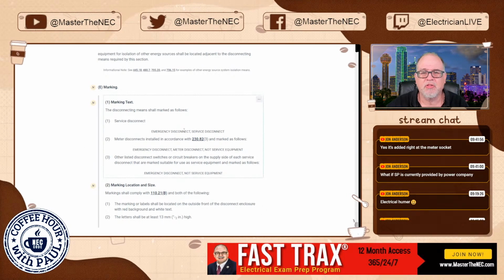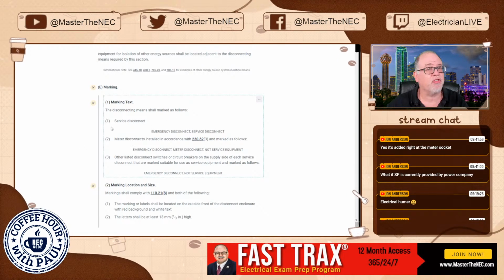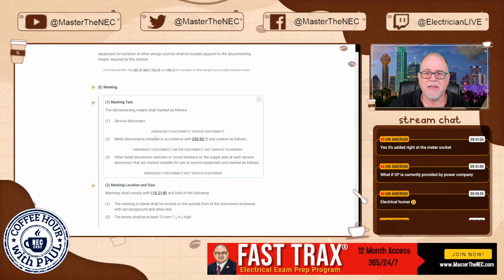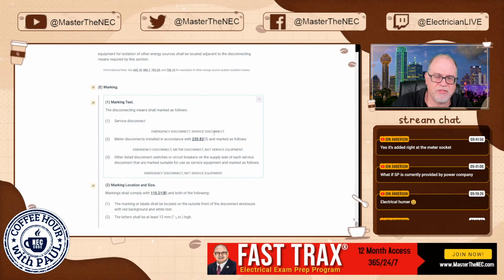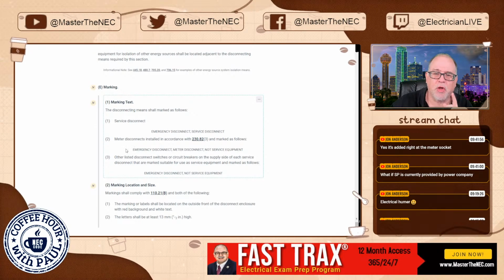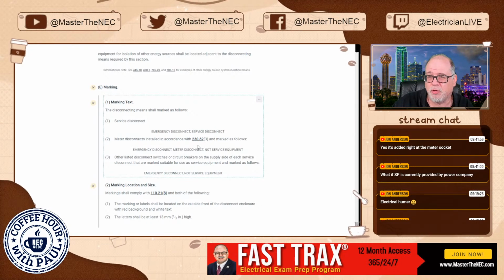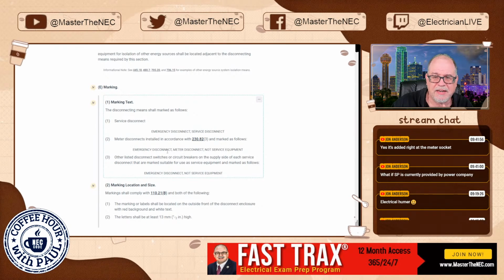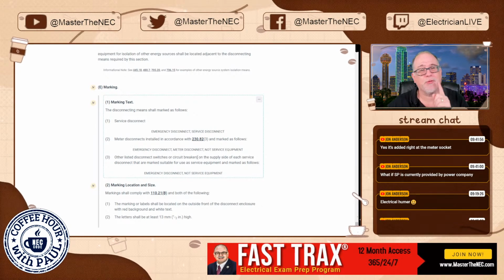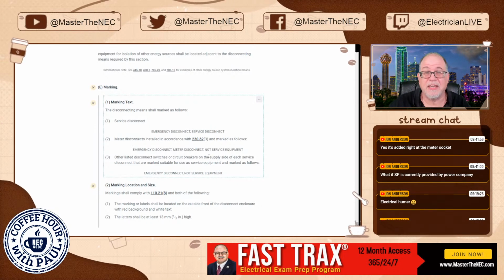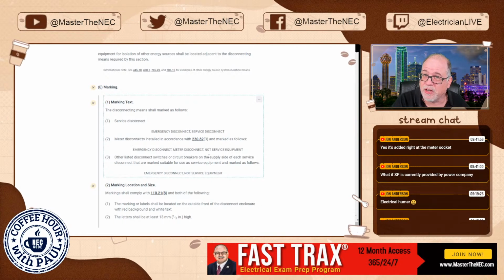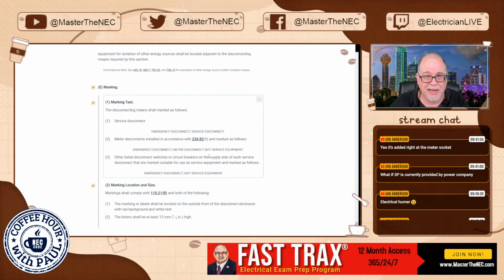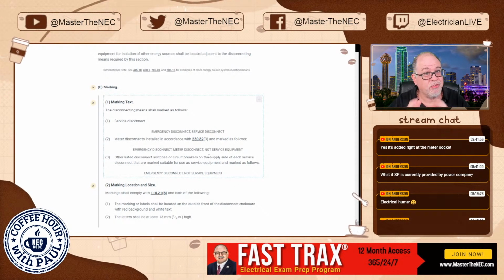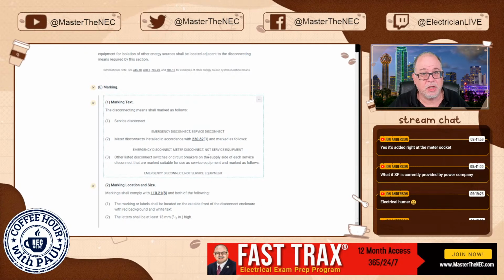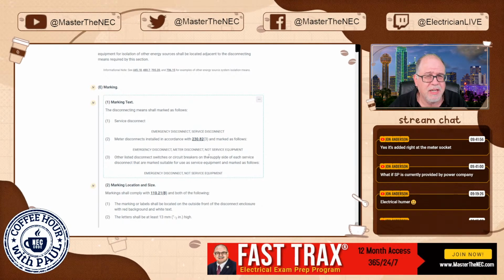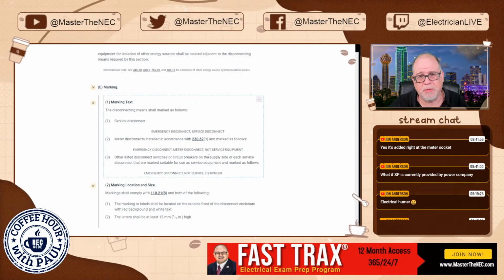Nope, they didn't disappear. So down here, if it's a service disconnect and it's also the emergency disconnect, remember the allowance we had before? Then you have to put labels on it, emergency disconnect and service disconnect, because it's serving two functions here, right? Now, those meter disconnects, the ones that are permitted by 230.82(3), you have to mark those emergency disconnect, meter disconnect, and you also have to remind everybody that it is not service equipment, okay? It doesn't go from service conductors to feeders after a meter disconnect, okay? Don't get confused. It's just a meter disconnect. These are very common in commercial applications, not so common in residential, but obviously allowed to be utilized, okay?